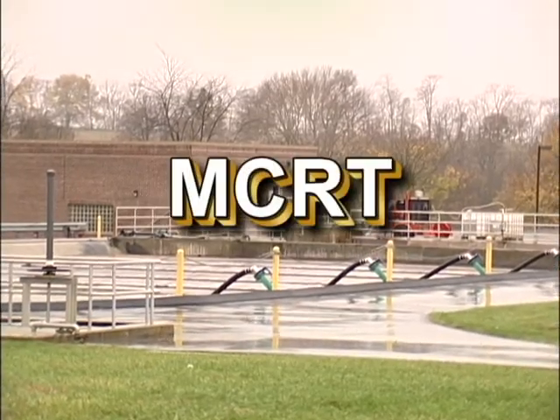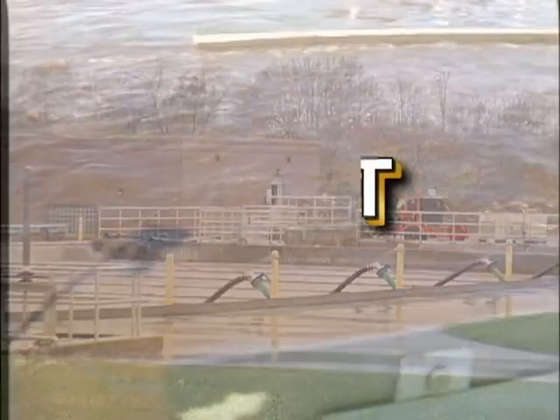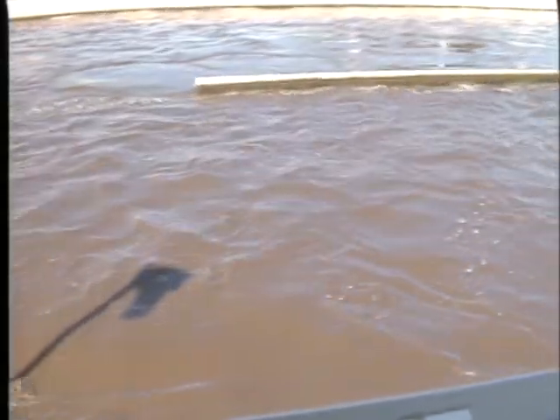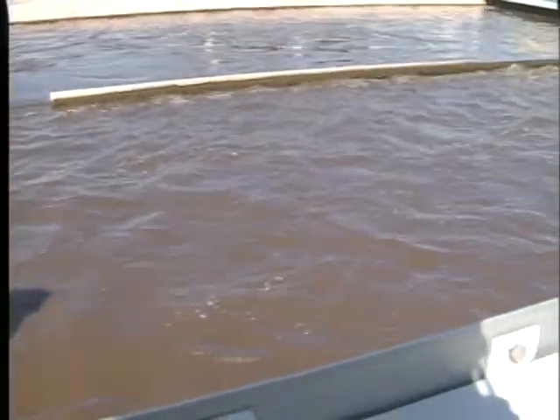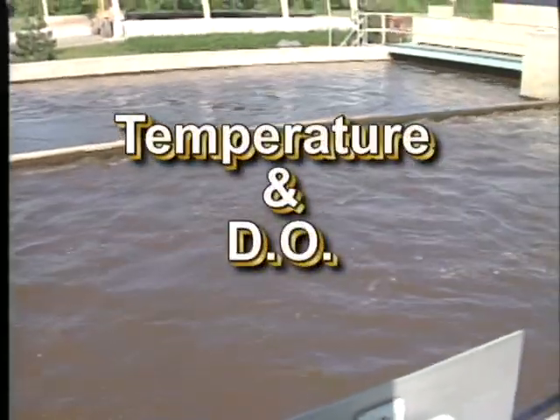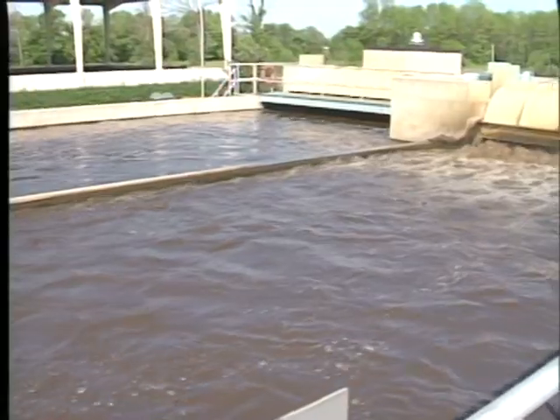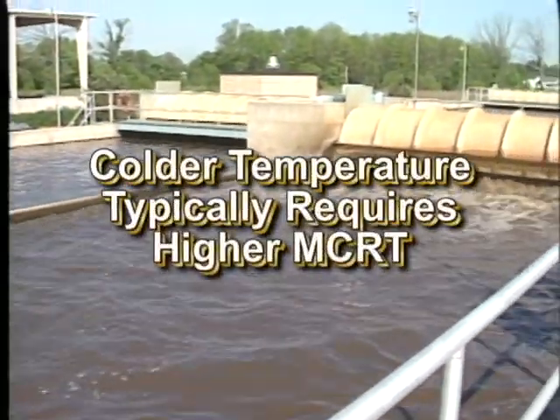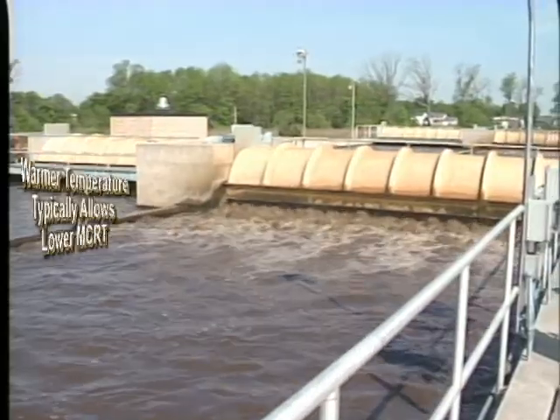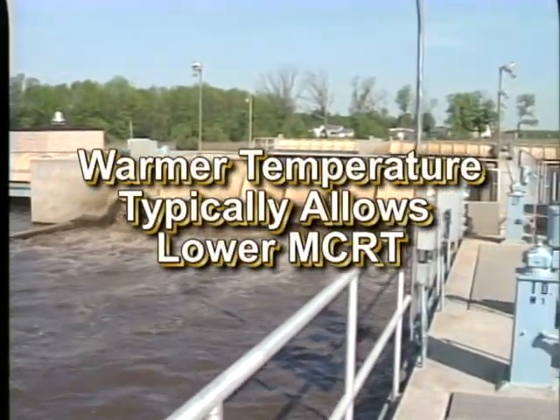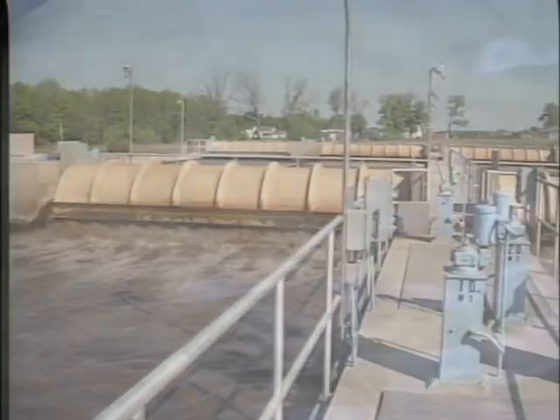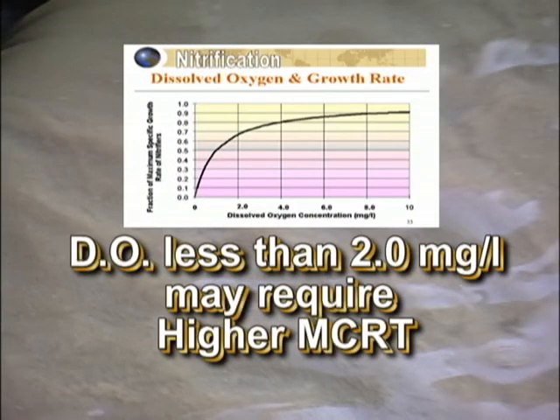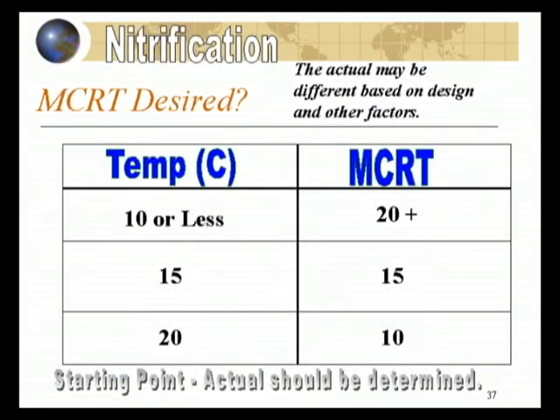Factor number 4, mean cell residence time. The actual required MCRT for nitrification depends upon the previous two factors, temperature and dissolved oxygen. During colder months, the MCRTs will need to be increased to achieve nitrification, while the increased activity during the summer months will allow for a lower MCRT. If the DO drops, the MCRTs will have to be increased to compensate as well. The following chart can be used as a rule of thumb. However, the actual MCRT should be calculated.